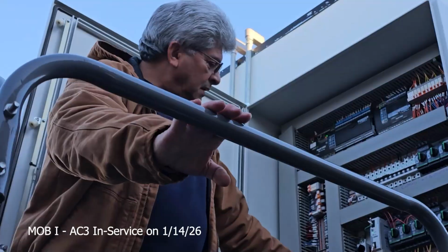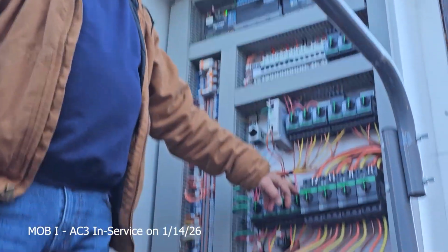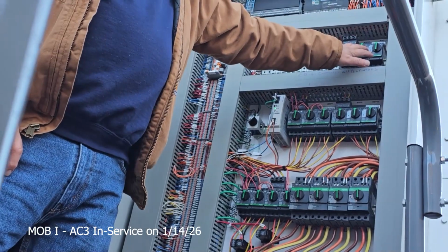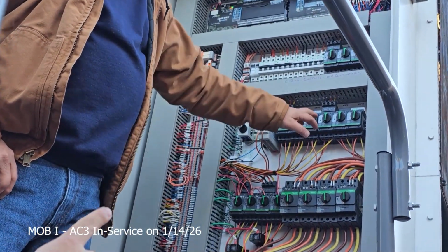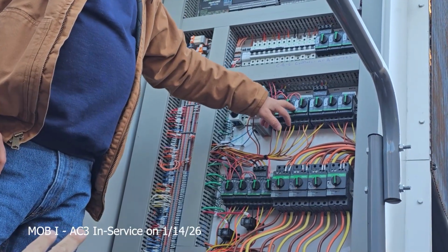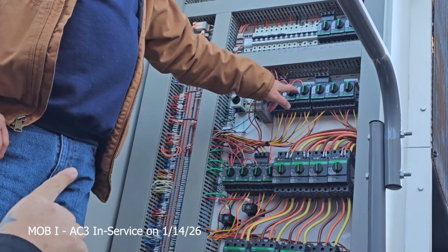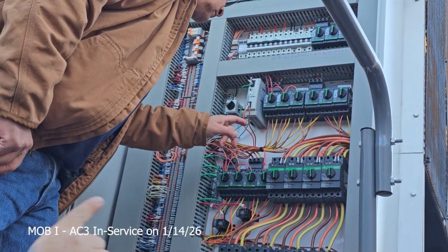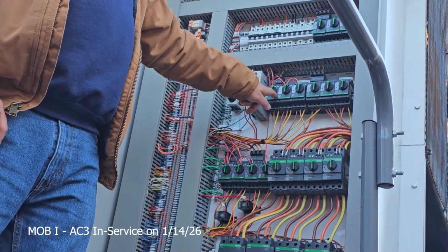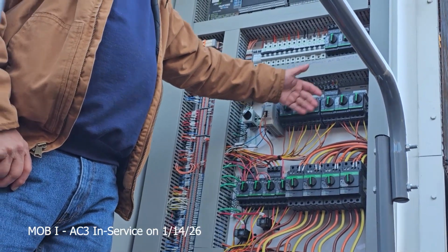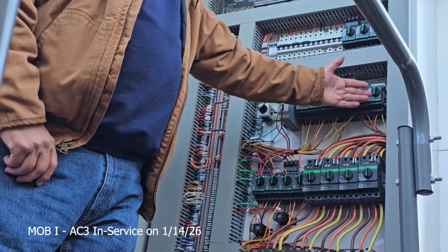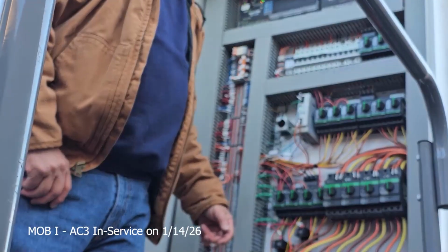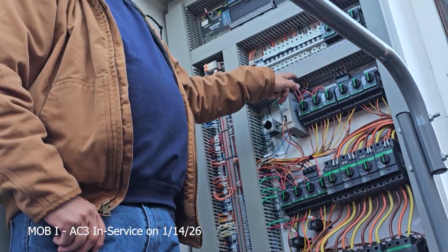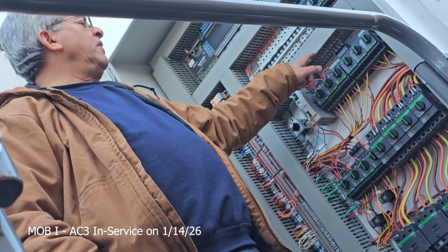Can you show me the breaker that you reset? Because if in the future it trips again, we know which one. These are your supply fans. These are return fans. The last 6 are axial fans, condenser fans. Those 3 on the left, they have it written down up there. Somebody wrote it down up there. RF1, RF2 on the cover. These 3 are your return fans, your MSB for return fans. Those are the axials and the top ones. So somebody did write out here RF1, RF2, RF3.